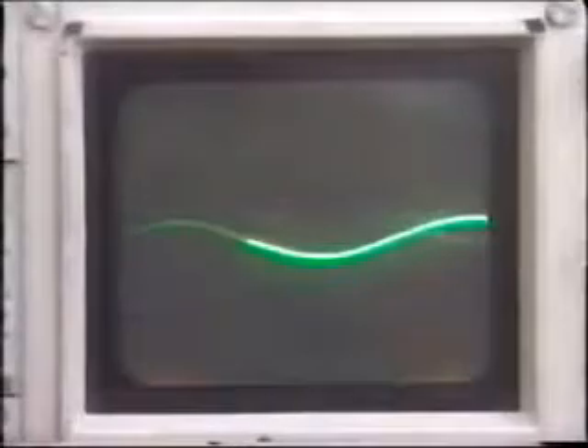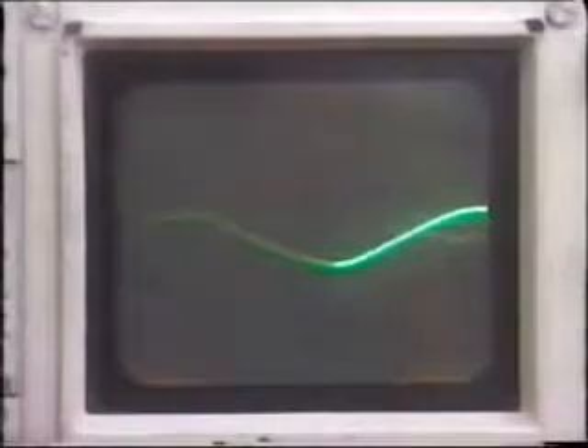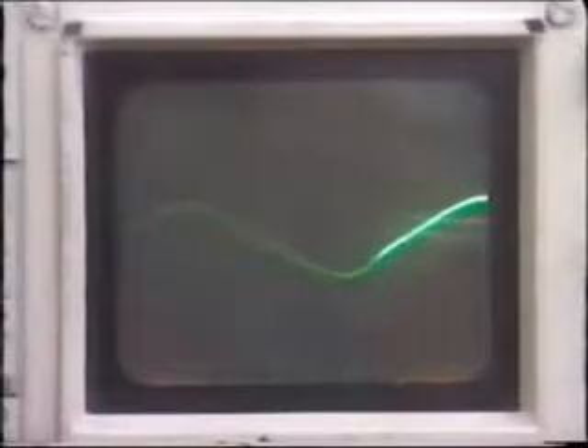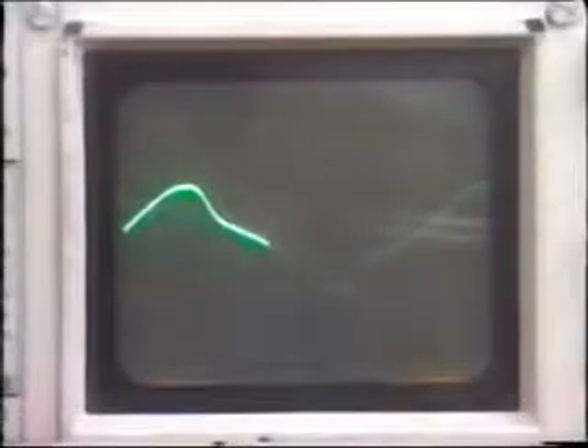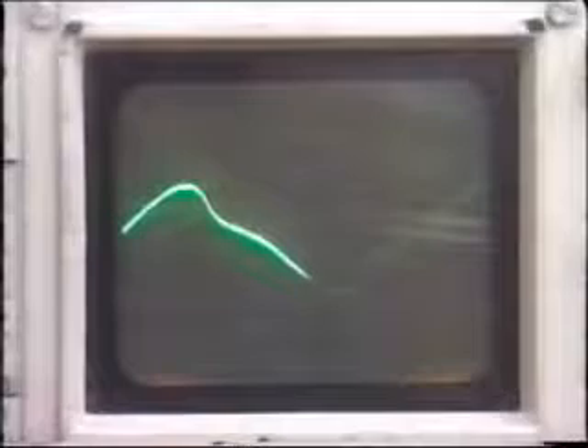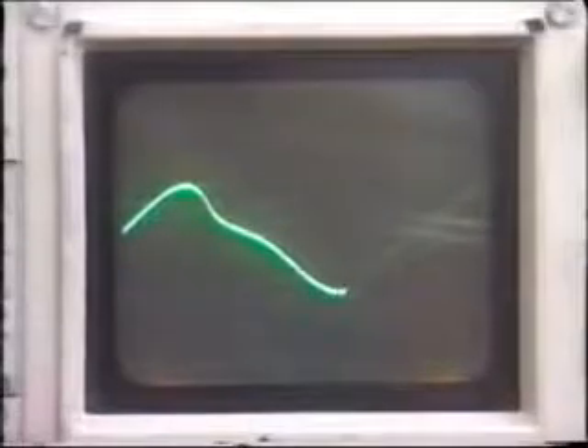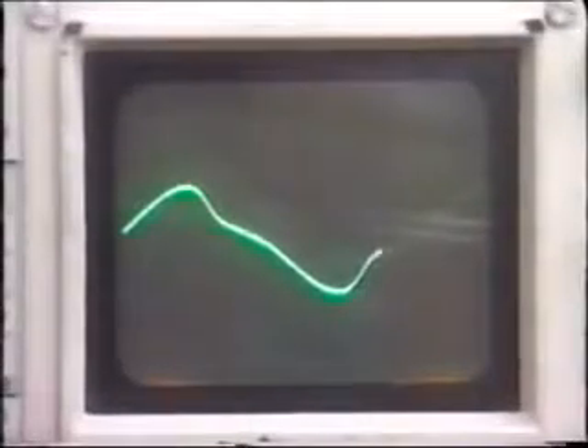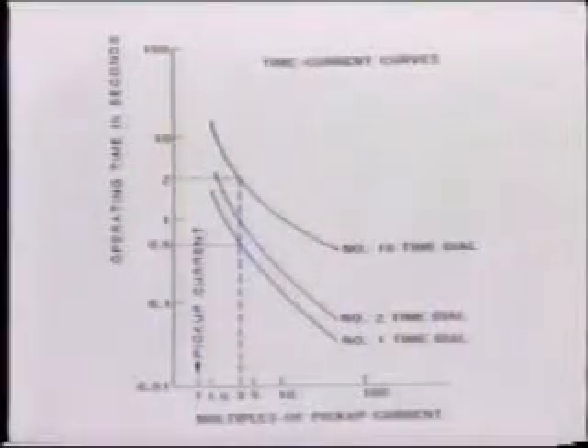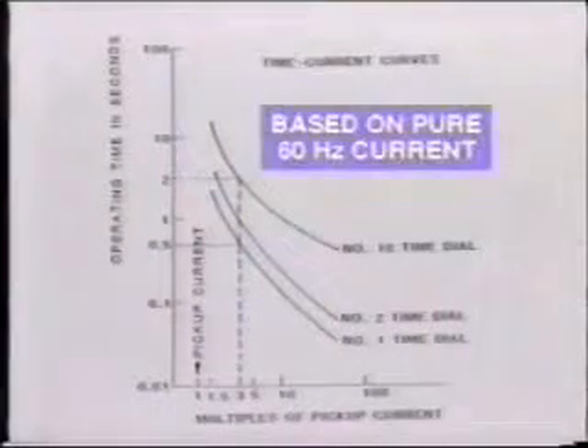As you start increasing the test current, you will see a clean sine wave at low currents. But as current increases, the wave shape starts resembling the surface of the moon. This visual proof tells you that the relay is indeed receiving distorted waveforms from the test set, and the test setup must be changed in order to achieve correct test results. The manufacturer's curves are based upon pure 60 Hertz current.